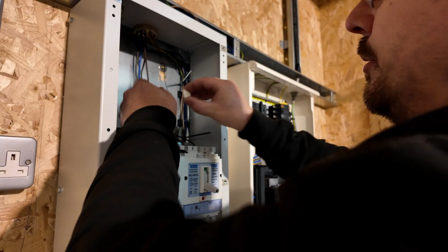It's a bit of a myth some people like to share around, that if you're bunching your cables inside switchgear there are extra considerations around derating, when usually it's taken care of anyway in the specification you'd use for your overcurrent protective devices and the containment leading around it. But hey, it makes for an interesting podcast topic and lets people sit on their perch of superiority towards others. In this case, we're going to have next to no load running through anything anyway, so it makes no difference.